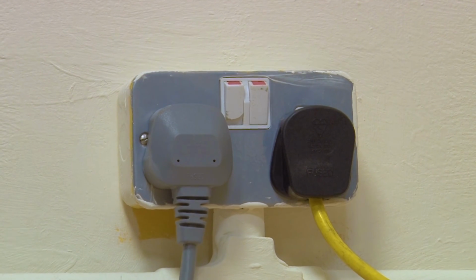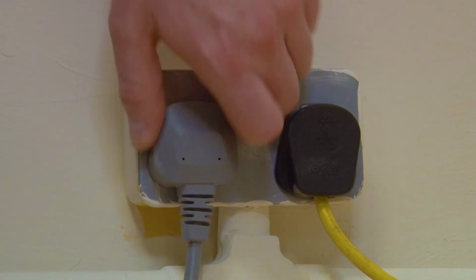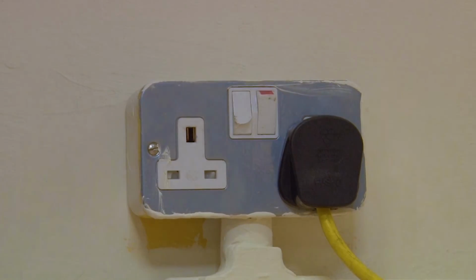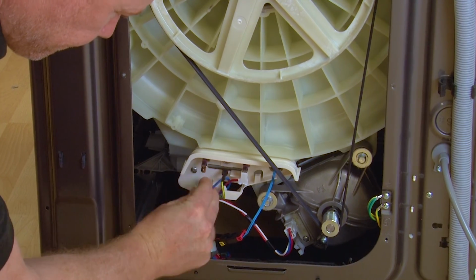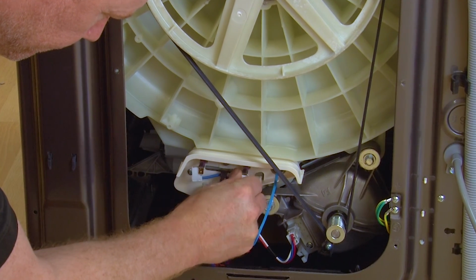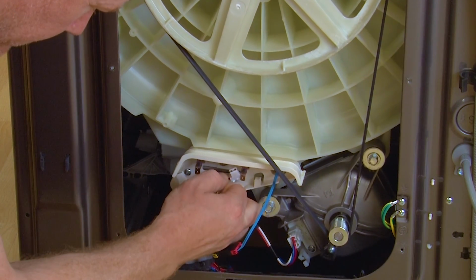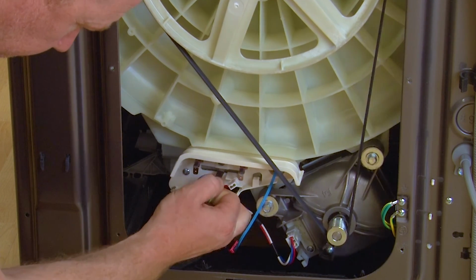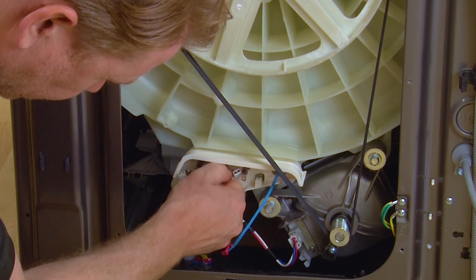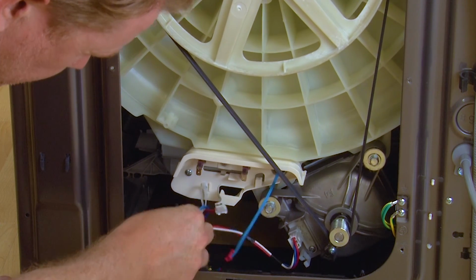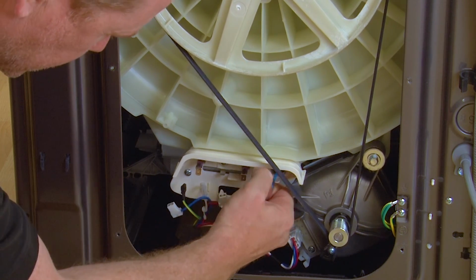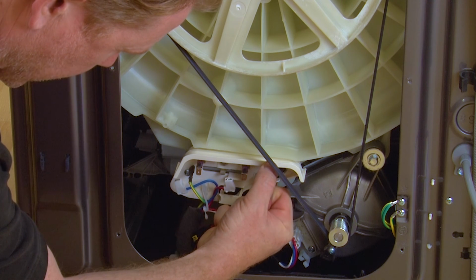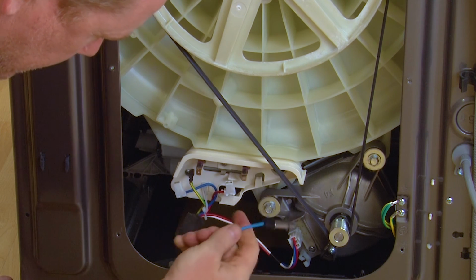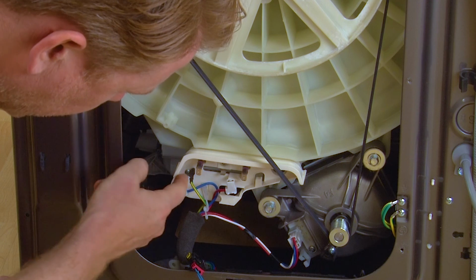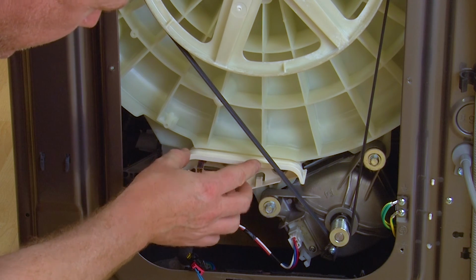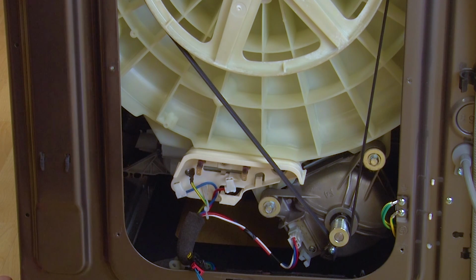Remember to unplug and disconnect the machine before carrying out any further work. Take the electrical connections off, then remove the thermostat, gently pulling it away from the housing, like so. Then undo that screw and take the housing and the heating element out.